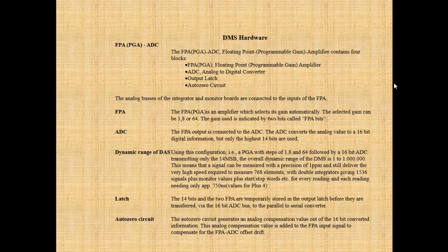This means a signal can be measured with a precision of 1 ppm, while still delivering the very high speed required to measure 768 elements with double integrators, giving 1,536 signals plus monitor values plus start/stop words for every reading, with each reading needing only approximately 750 ns. The 14 bits and the 2 FPA bits are temporarily stored in the output latch before transfer via the 16-bit ADC bus to the parallel-to-serial converter. The AutoZero circuit generates an analog compensation value from the 16-bit converted information and adds it to the FPA input signal to compensate for FPA/ADC offset drift.